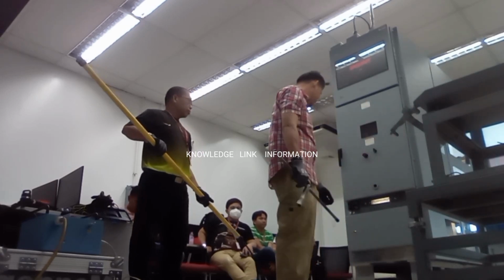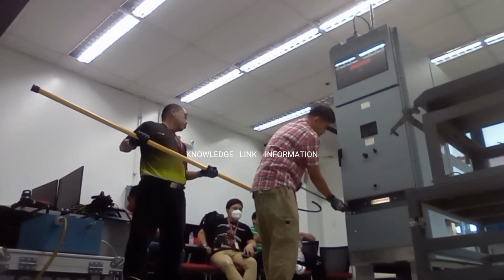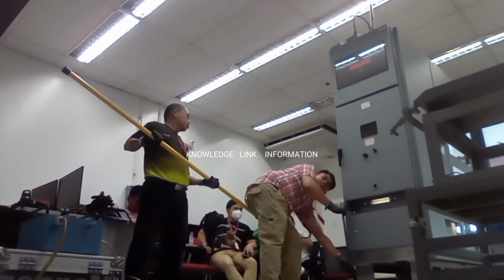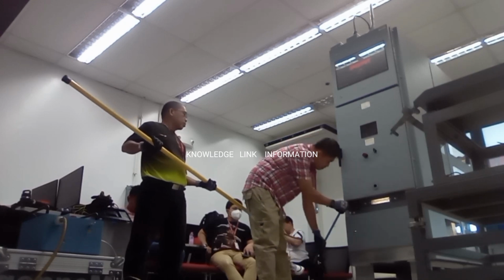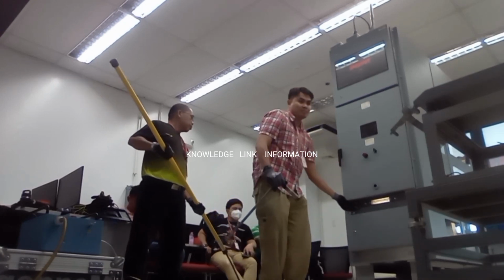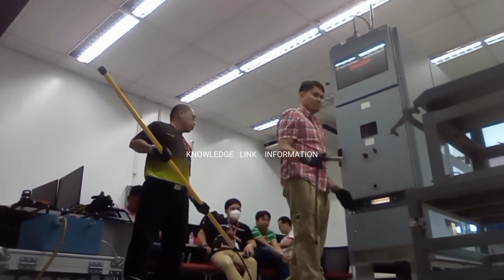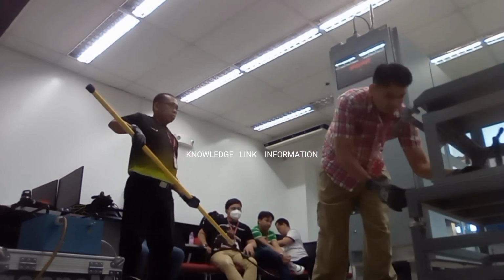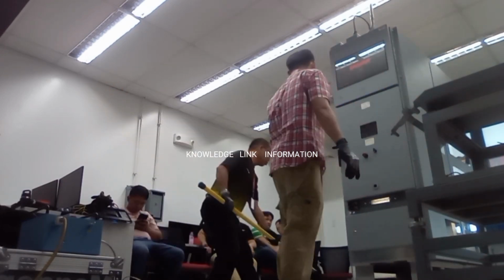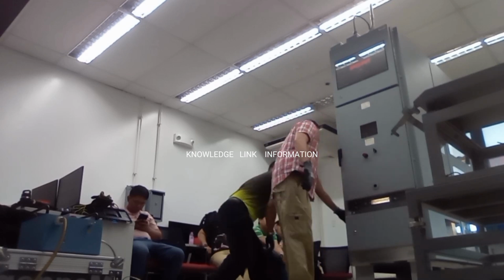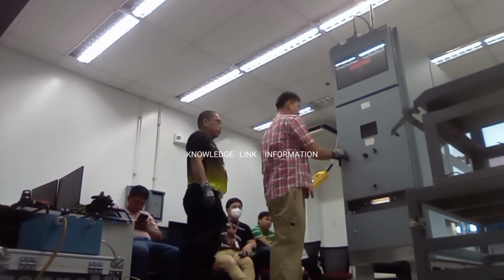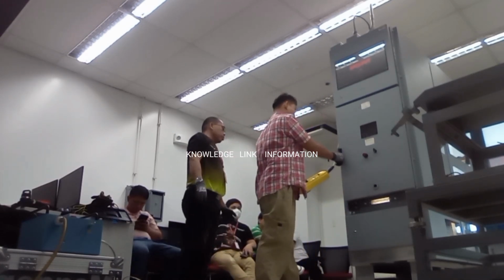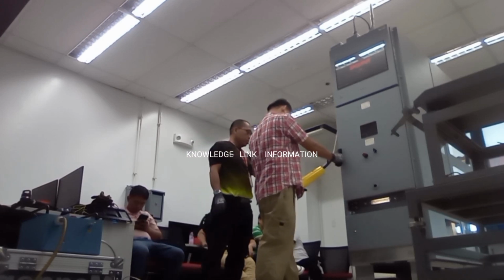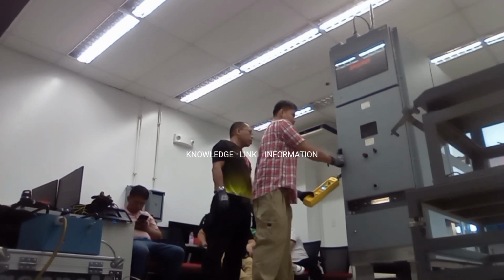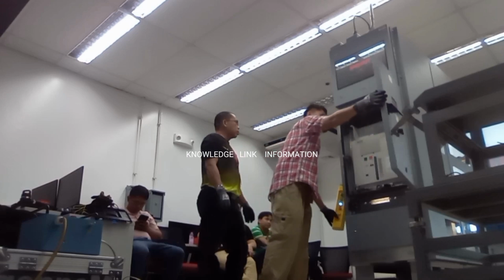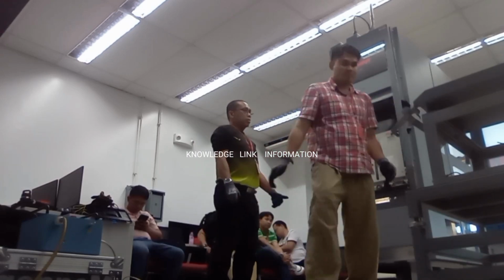Number 5. Use another special tool to connect the circuit earthing switch from the 3-phase busbar to the ground. Take note that we cannot connect the earthing switch if we do not fully rack out the high-voltage circuit breaker. Number 6. Open the switchboard by means of the push-button lock release. Remember that we also cannot open the switchboard door if we do not connect the circuit earthing switch, because of the safety interlock features of the switchboard.